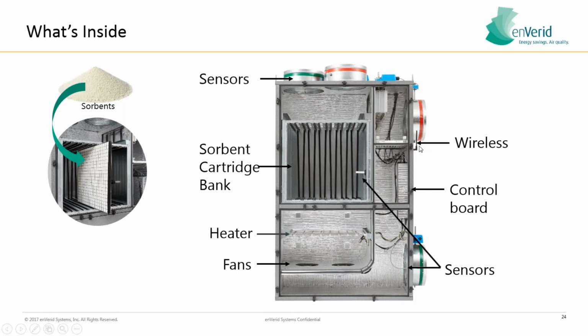All of this wireless component and information on indoor air quality is included in the annual cost of cartridge changeout. So you do have to replace these cartridges once a year. Once a year is manufacturer spec. It's basically the same as changing a filter on a building. The cost of that is typically the equivalent of around 25 to 30% of the average annual energy savings you're achieving. Usually that can be calculated by the fact that each one of our devices reduces outside air by 2,000 to 3,000 CFM.